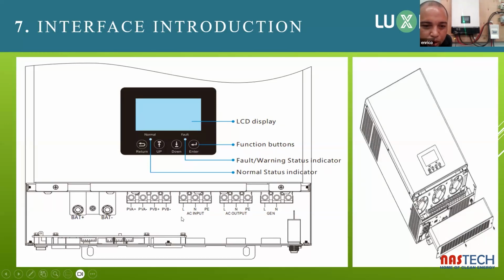The AC input will come from your changeover switch, and then your AC output will go to an output circuit breaker of about 20 or 25 amps. The recommendation is between 20 and 25. I would put a 20 amp because the maximum is 22 on the output side. So between the load and the machine, there should be a breaker as well.